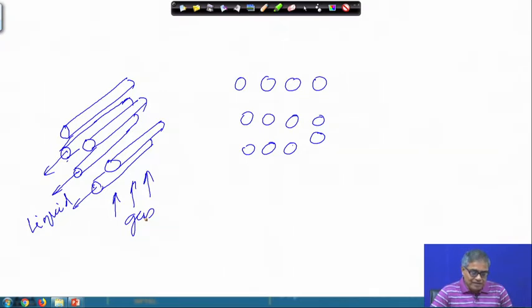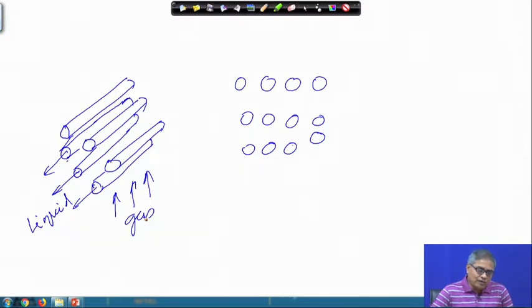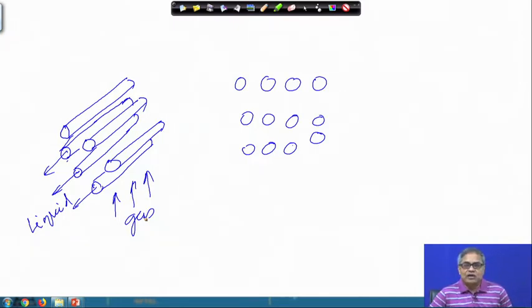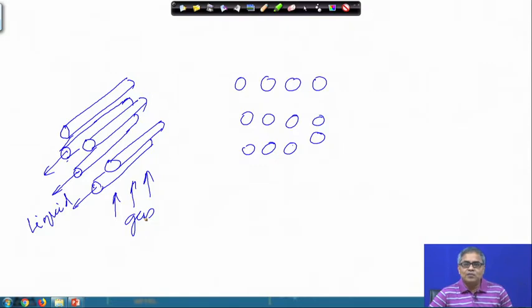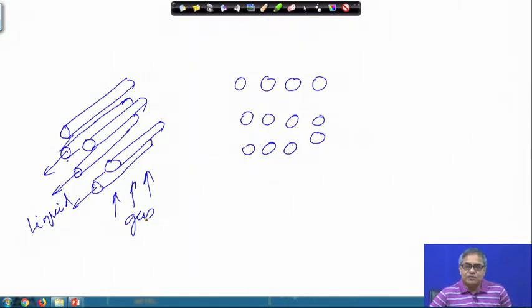In many cases these bare-tube heat exchangers are used because of their low cost. Since they have no fins, they give very little pressure drop, and the tubes can be cleaned easily. So where dirty gas must be handled and maintenance is a concern, this kind of heat exchanger is preferred.